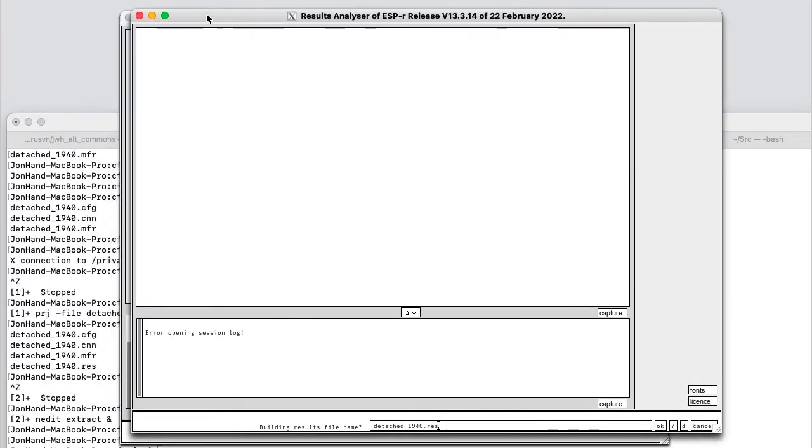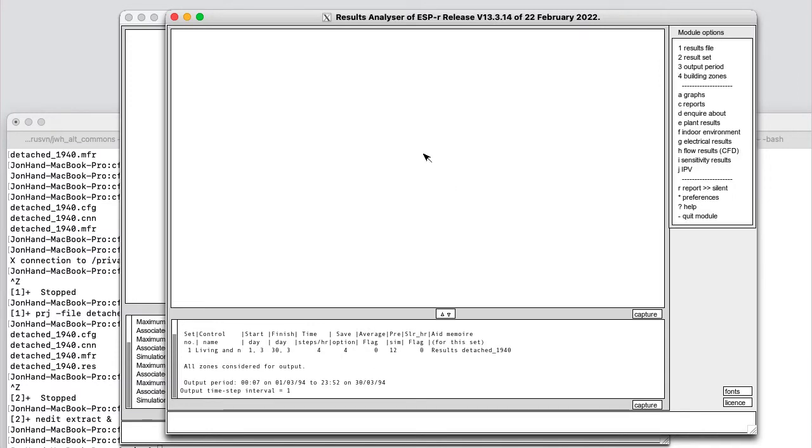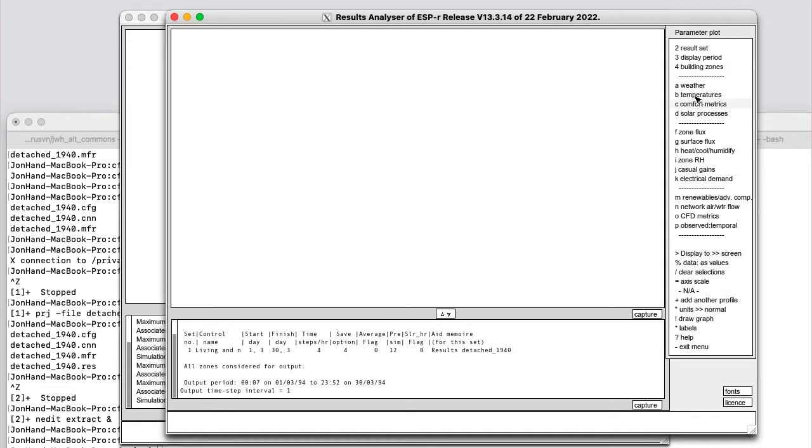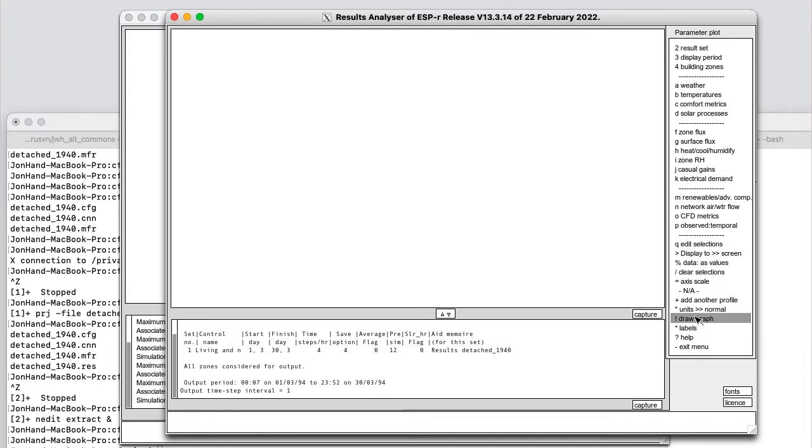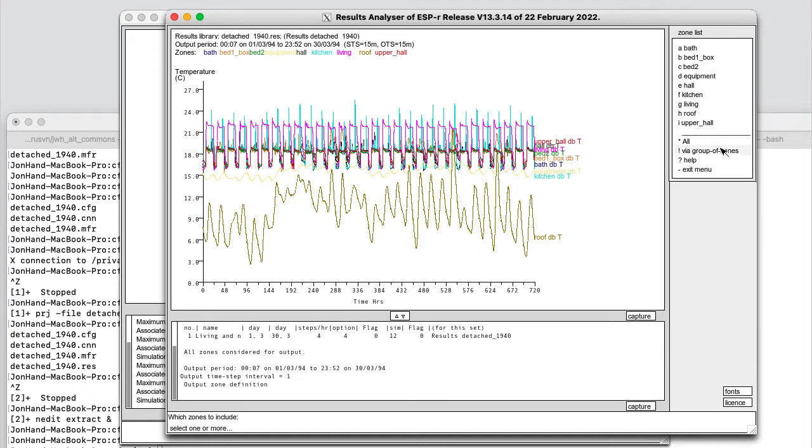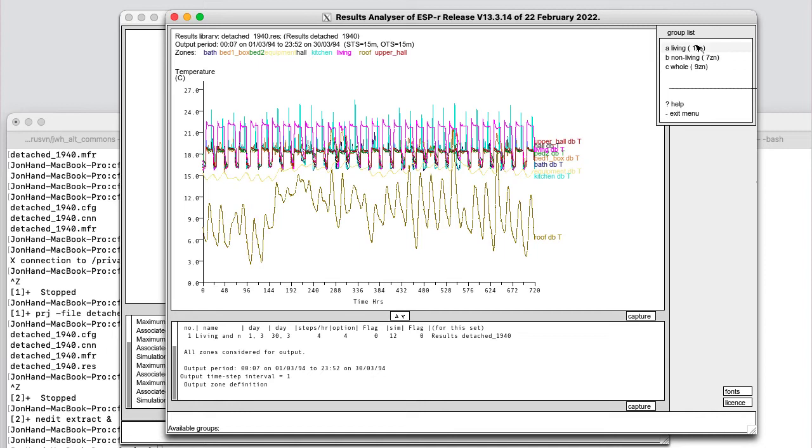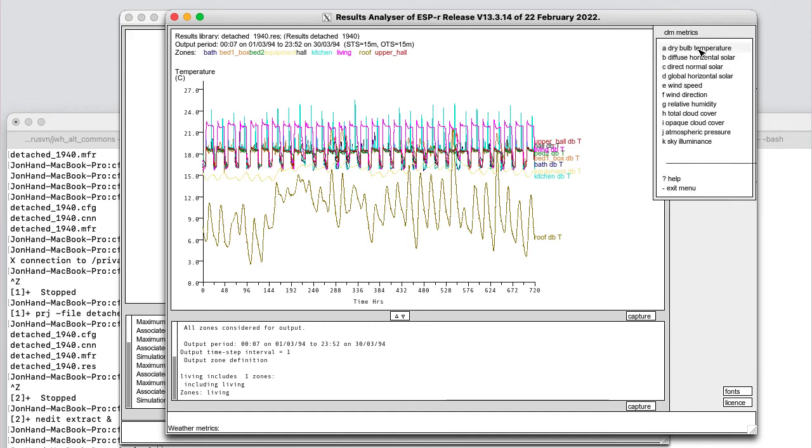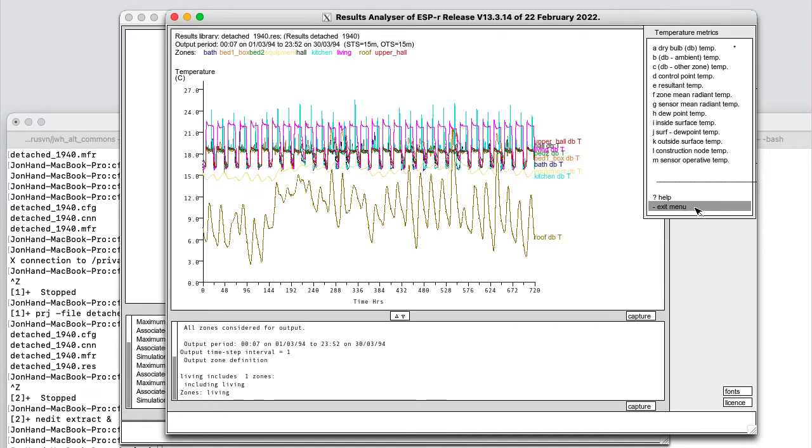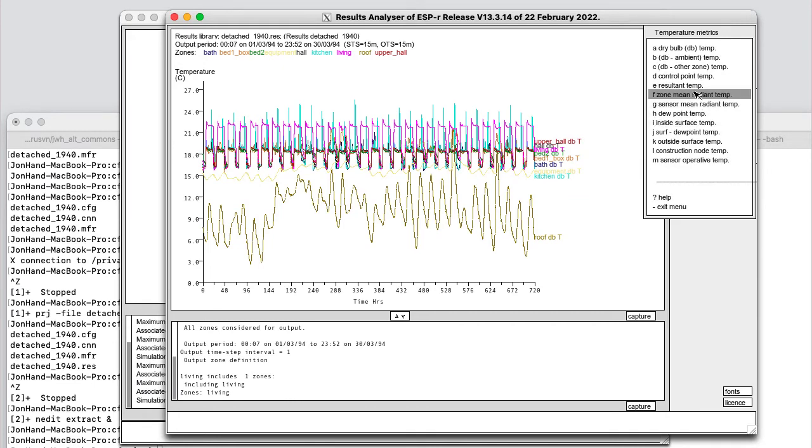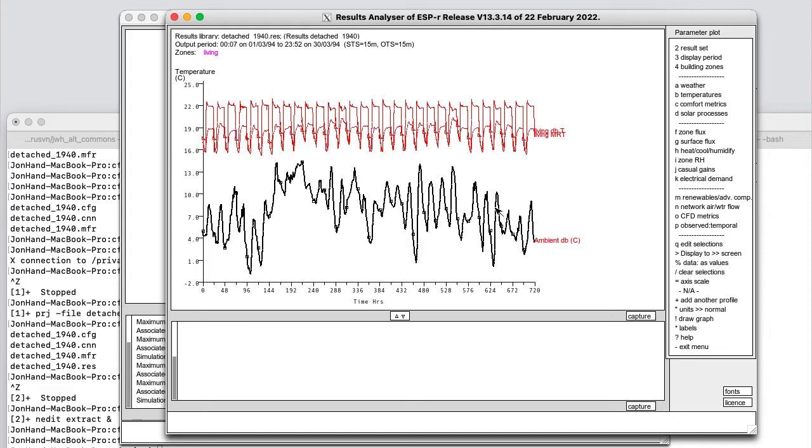That would then be passed the name of the just completed results file and open up. In an interactive mode, I might go into the graphic area to parameter plots and, for example, look at dry bulb temperatures and draw that graph. So I'm seeing many things that I would expect to see, but I might also want to go and focus in on the living space itself. Clear the selections. Let's look at the dry bulb temperature outside as well as the temperatures inside. And to get an idea of comfort, let's look at zone mean radiant temperature and draw that. Now I see there's a difference between the dry bulb and the mean radiant temperature.